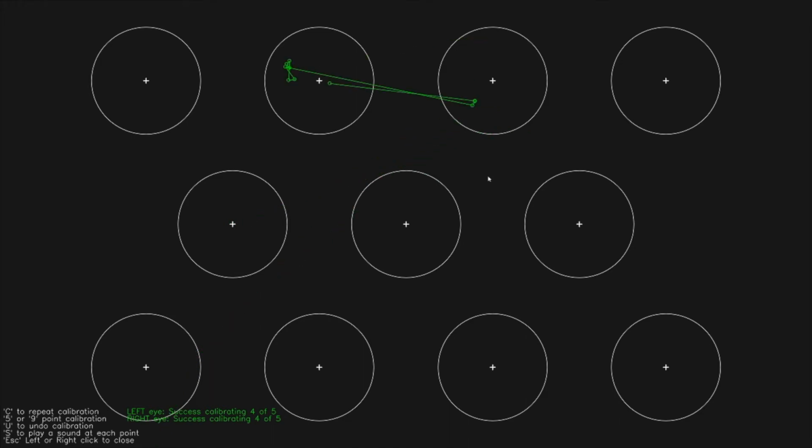Your accuracy level must be 4 out of 5, ideally 5 out of 5 for each eye in order to achieve an accurate reading. If you do not pass the calibration test, use the window in the Control application and adjust the camera to make sure the user is centered in the top square and that each eye appears in the lower squares. You may want to sit back from the camera for the best readings. Don't sit too close to it. Once the user's gaze is calibrated, you are ready to begin collecting data.